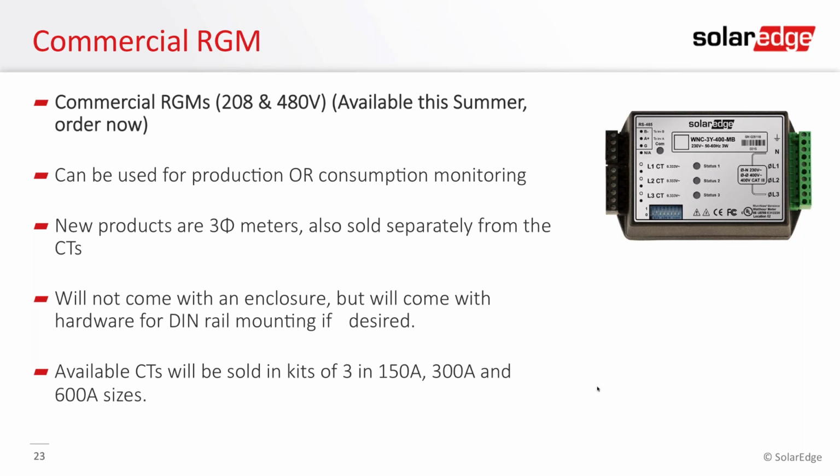Okay, so the physical wires, you'd have a bundle that's around 600 and a bundle that's less than 300, and put the CT clamps around those wires. Correct. Not necessarily a bundle, but if you think of it in terms of a branch circuit where you're bringing multiple inputs into one line, you're going to combine it at, for instance, a distribution panel, and then clamp around the output of that distribution panel back to a main service panel.